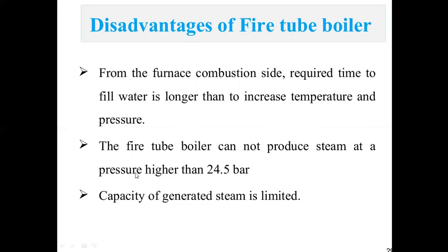The fire tube boiler cannot produce steam at a pressure higher than 24.5 bar. That means it is used for smaller capacity applications, and beyond that we may not use 5-tube boilers. The capacity of generated steam is limited, so steam generation capacity is also less for the fire tube boiler. These are its disadvantages.